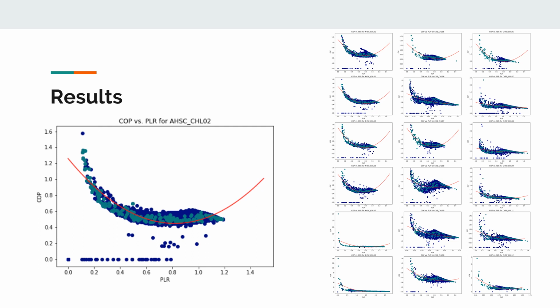In order to counteract this issue, a sample size of 200 randomly selected points was chosen to perform the regression calculations. The sample points were chosen from a uniform distribution across the PLR range of the data. Because the points are chosen uniformly, the regression is able to capture the true shape of the efficiency curve for each chiller because all intervals in the PLR range are equally represented. The results of these regressions are utilized in the Lagrangian optimizer to relate an optimal coefficient of performance back into an operator-usable PLR value.